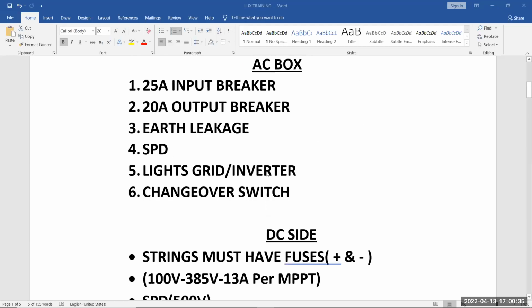That's basically for my AC side. Now, at this moment, 4 mil wires is more than enough on an inverter. 2.5 is also fine. But as soon as you parallel the two inverters, the AC output of the two inverters will have to go to a 4 or 6 mil output to your main breaker. But if it's possible, I like to do all my electrical work from the inverters and so forth with 4 mil to an earth. That's what I like to do. I know it's slightly more expensive, but I like to have my wire slightly thicker than necessary, so I know everything is fine in this instance.